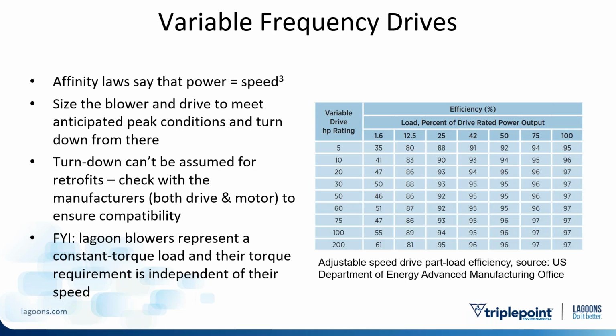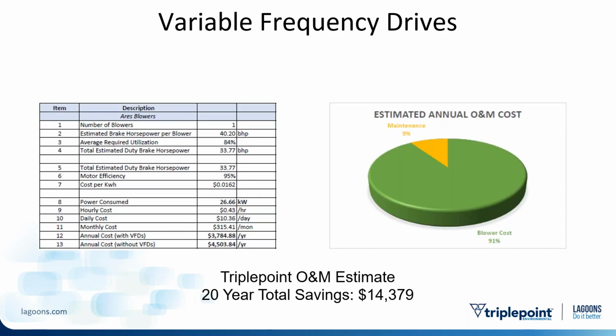So looking at what it costs to run a lagoon blower and thinking about VFDs is my next slide here. And this example is one that we put together for a customer that wanted to model how their system would run and what it would cost to run. So over on the left, we've got a single blower in this model, and it's about 40 horsepower. 84% is all the utilization that's going to be required, so that's going to mean we're going to really be at about 33.77 on the brake horsepower with a 95% efficient motor.